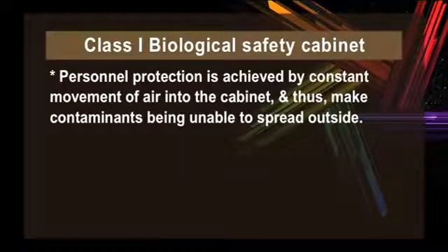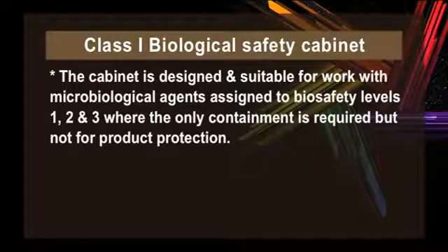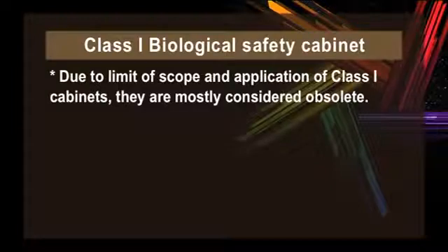Personal protection is achieved by constant movement of air into the cabinet, thus making contaminants unable to spread outside. The cabinet is designed and suitable for work with microbiological agents assigned to biosafety levels 1, 2, 3, where only personal protection is required but not product protection. Due to the limit of scope and application of class 1 cabinets, they are mostly considered obsolete.